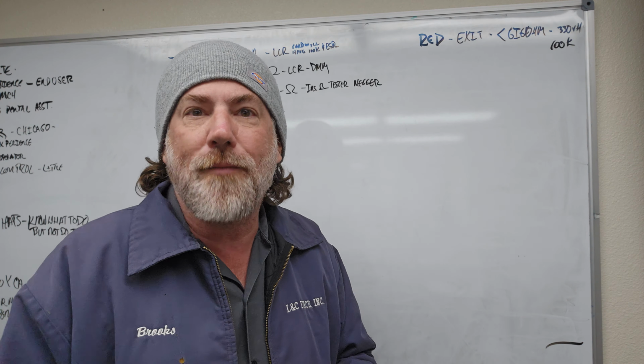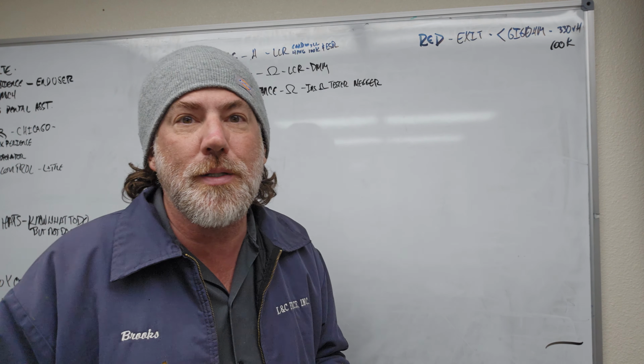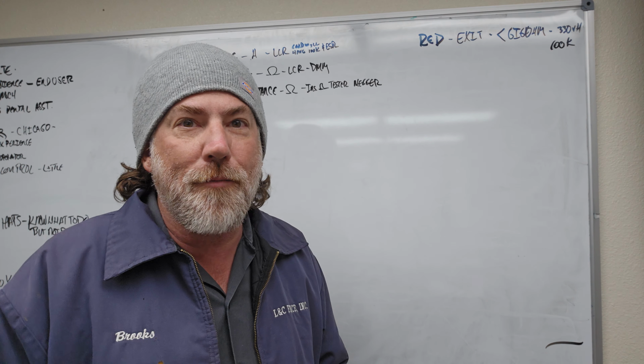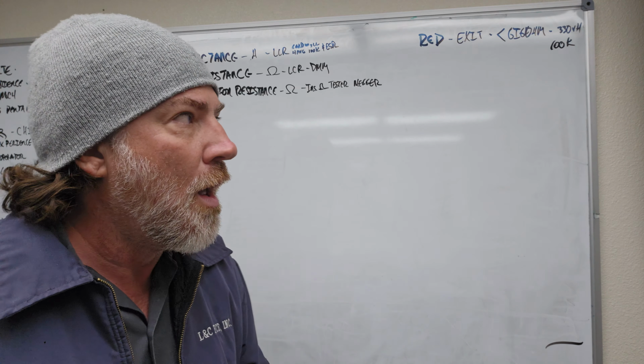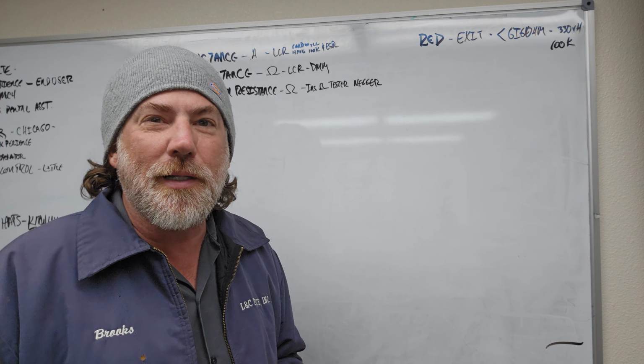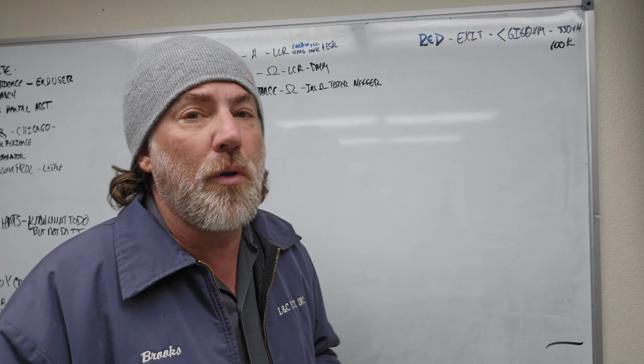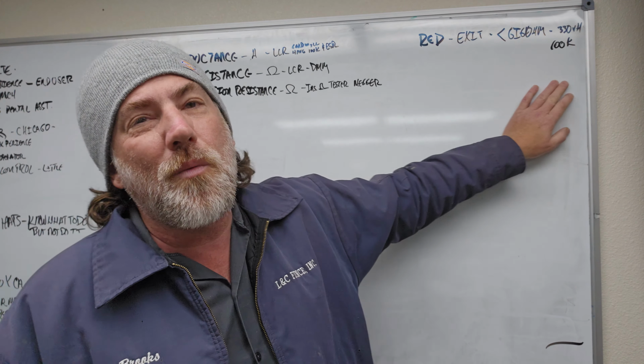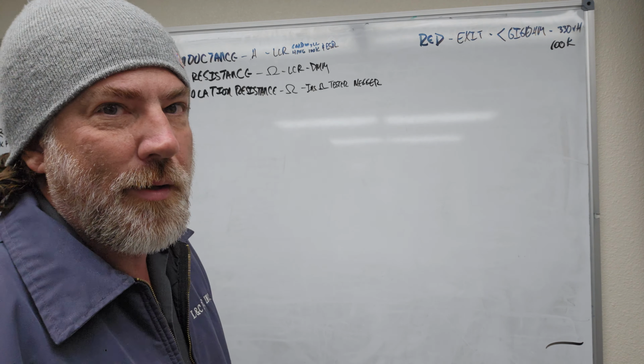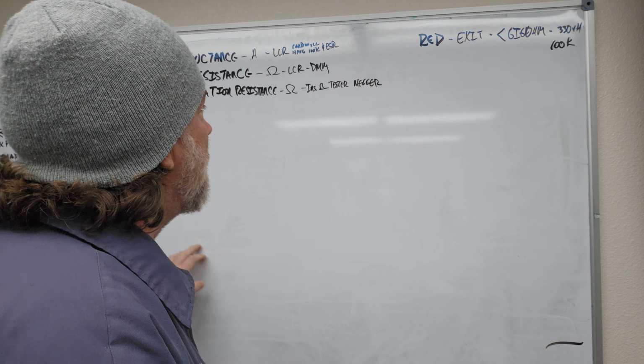And that's another thing. You could have a bad ground, still test the insulation resistance to be good, but because you have a bad ground, you'll never know. I used to back in the day mark where I actually would test ground. I still do that on AC motors, but I don't do it on loops anymore. And every once in a while, I'll also write down the equipment that I use to document it as well.